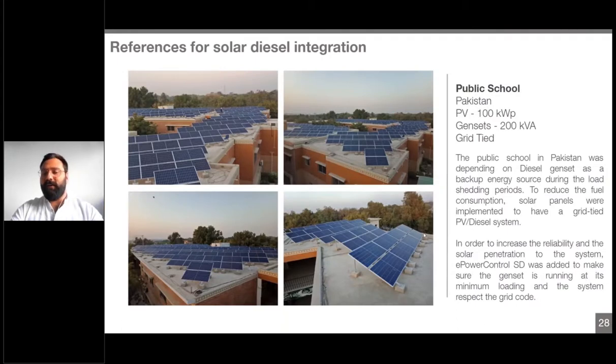Also in Pakistan, we did several projects. We have more than 20 projects already installed. This one was for a public school in Pakistan. For this project specifically, we were able to provide net metering, so the operator let us inject into the grid. Once the grid is available, all the extra PV is injected into the grid, and for sure, once there is a switch to the genset, we provided the minimum genset loading.